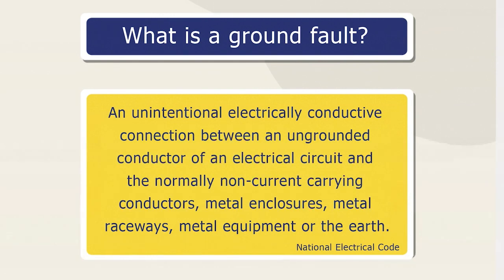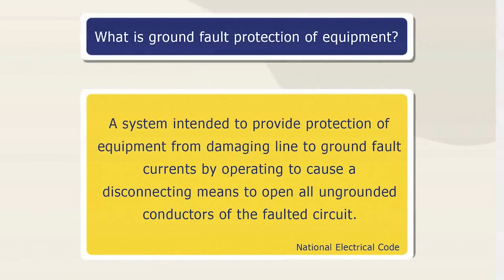The National Electrical Code defines ground fault as an unintentional electrically conductive connection between an ungrounded conductor of an electrical circuit and the normally non-current carrying conductors, metal enclosures, metal raceways, metal equipment, or the earth. Further, the National Electrical Code has a definition for ground fault protection of equipment. It's a system intended to provide protection of equipment from damaging line-to-ground fault currents by operating to cause a disconnecting means, that's going to be your main breaker or your main switch, to open all ungrounded conductors of the faulted circuit. The ungrounded conductors, that's going to be your phase conductors.